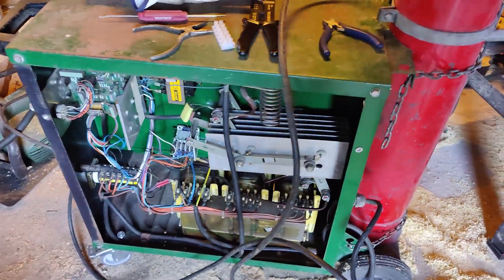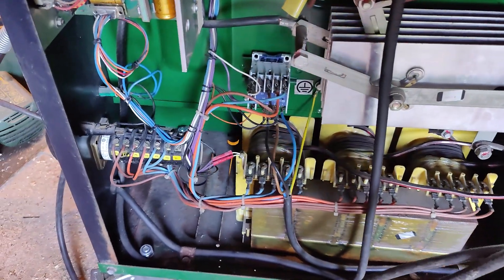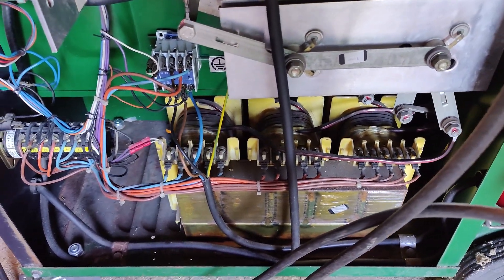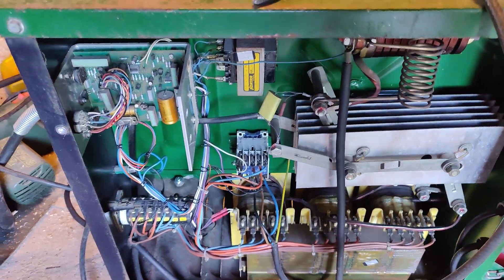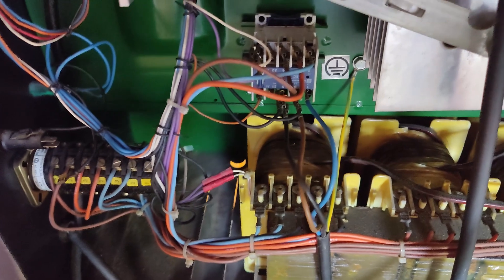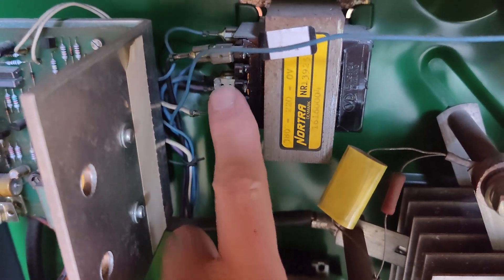What I have here is a Migatronic Danish Welder AutoMIG 200X. The issue I have is that this is wired for 380 volts three-phase. I've got 220 volt three-phase and what I'm told to do is I need to change this connector up to here.